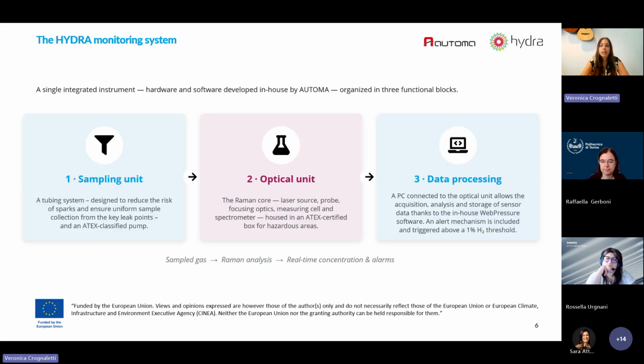The Hydra monitoring system is a single integrated instrument. Both the hardware and software parts are developed in-house by Automa, and the monitoring system is organized in 3 functional blocks. The first block is the sampling unit. It is composed of a tubing system and an ATEX classified pump. This part is designed in order to ensure uniform sample collection from the field and so from the key leak points. The second part is the optical unit, so the Raman core of our sensor, and it is based on a laser source, the probe, the focusing optics, so both lens and windows, the measuring cell, and the spectrometer, of course. All of these parts are housed in an ATEX certified box, able to work also in hazardous areas.